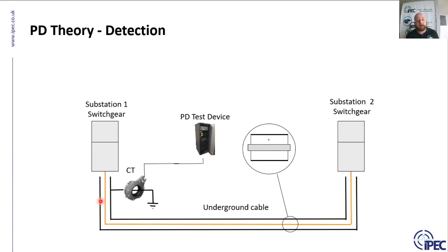So on medium voltage networks like this one here, HFCTs tend to be installed in the cable termination. They're installed back in the substation, and quite often they're installed on the earth sheath, particularly for spot testing, because the earthing tends to be more accessible. So that's where HFCTs tend to be installed. You can install them on the core, and in fact on the core you would get a more accurate signal. You'll be able to detect PD a little bit lower if you install it on the core. However, that's not always possible depending on the makeup. A shutdown is required for that installation, so it tends to be on the core when it comes to a permanent solution, whereas installing for a temporary application tends to be focused on the earth sheath.